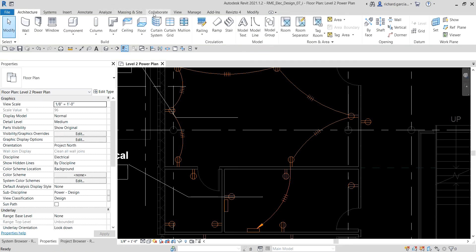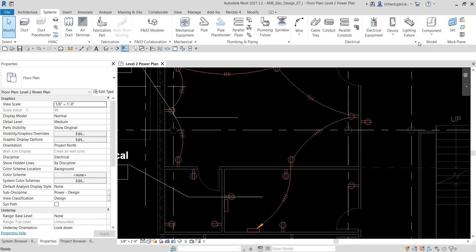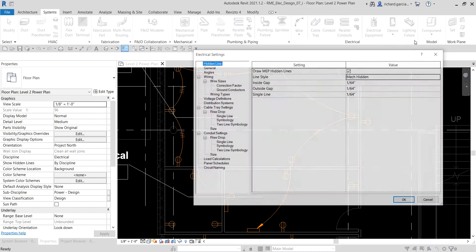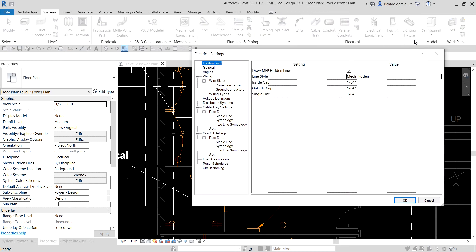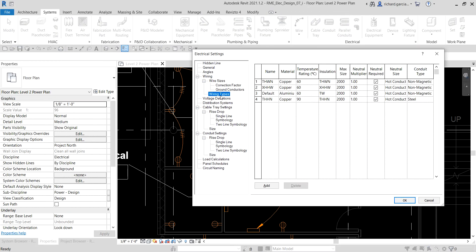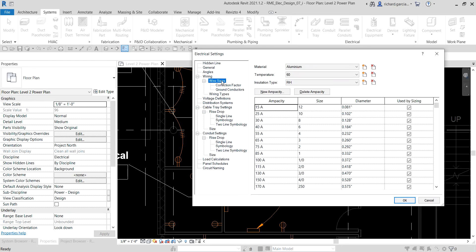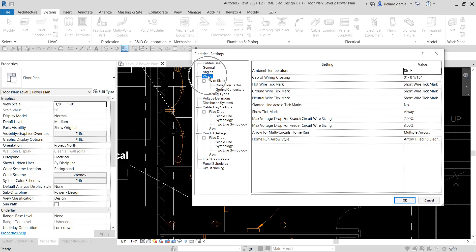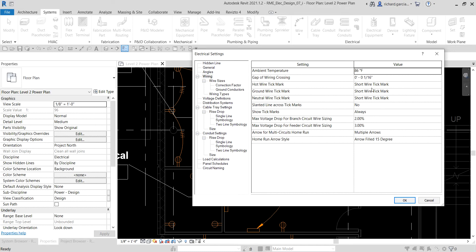If I click this home run, I can see: hot conductors = 2, neutral conductors = 1, ground conductors = 1, so the total is four tick marks. If I go to Electrical Settings under Systems, I can see the wiring types. Under Wiring I can see that for my hot, ground, and neutral wire I only have the short wire tick mark.